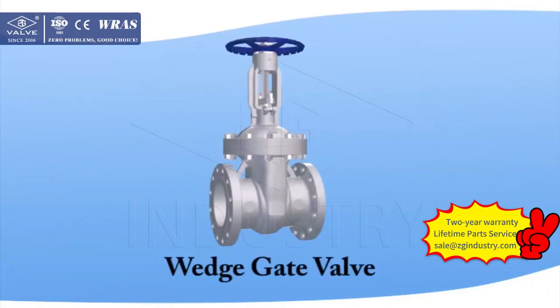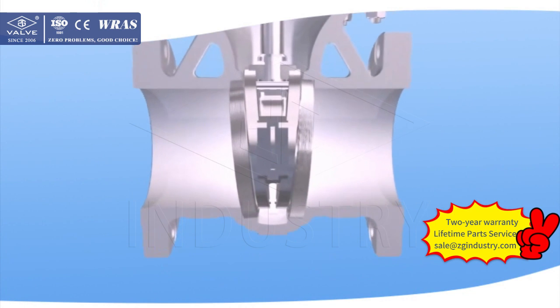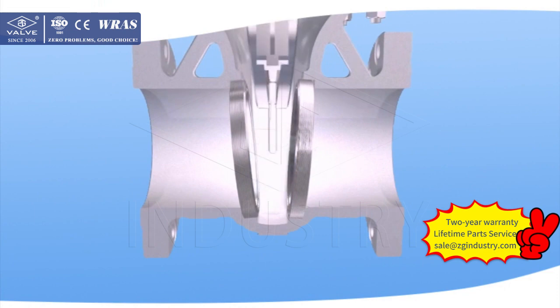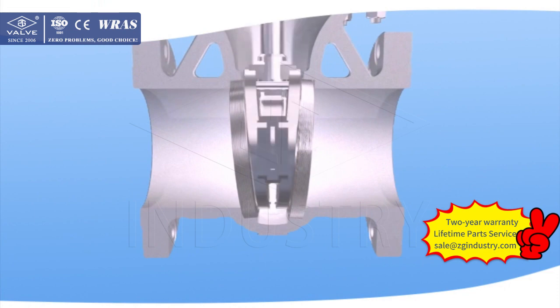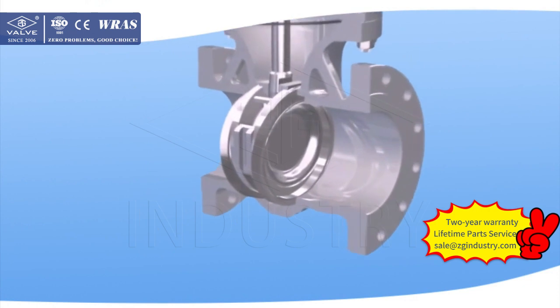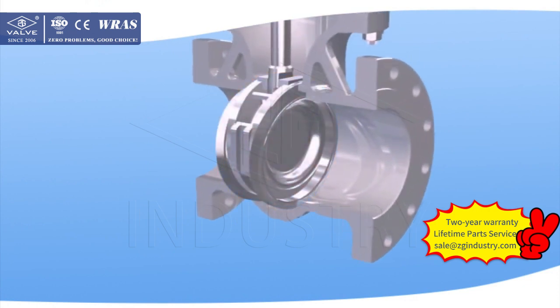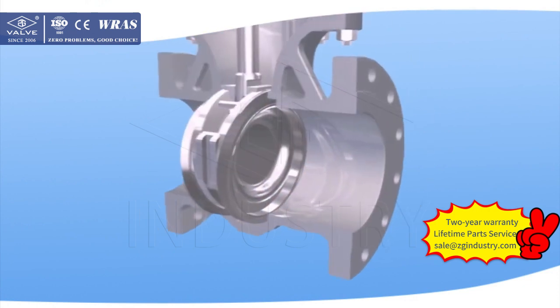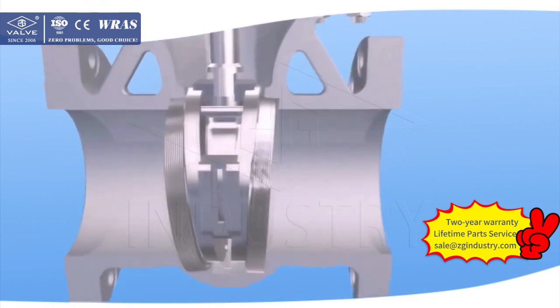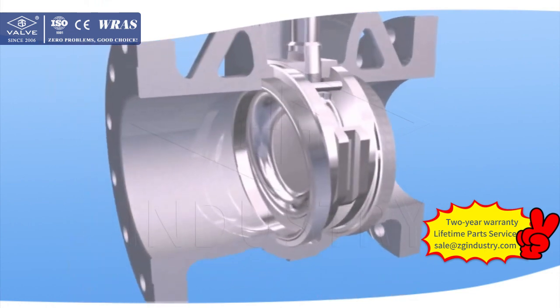Wedge Gate Valve. The trim of a wedge gate valve is a wedge, which is perpendicular to the medium flow direction. A gate valve can only be fully open or closed and cannot be used as an adjusting valve. A wedge gate valve can be a solid, inflexible disc type, and can also be a flexible wedge.